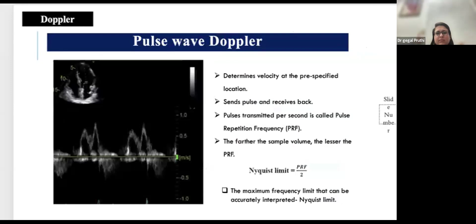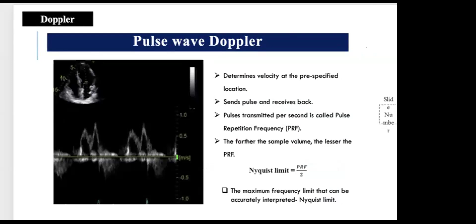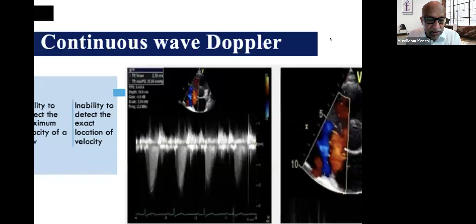So we can see that spectral Doppler is velocity versus time. Here you can see this will be the maximum velocity. You can move the cursor and see what the maximum velocity is here. In pulse wave Doppler, since we can exactly identify from where we are getting the velocity, we can use the window to pinpoint where we want to get the velocity. You can place this sample volume at the place where you want to know what's happening. That's the advantage of pulse wave Doppler. The disadvantage is that only low flow velocities can be measured with this. For high flows, we need to go for continuous wave Doppler.